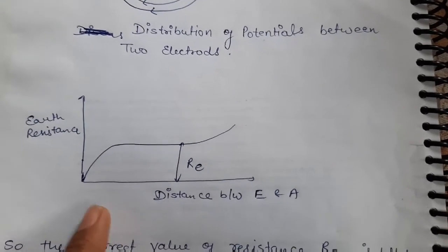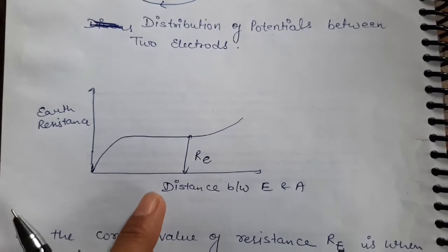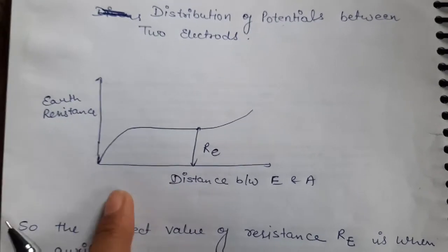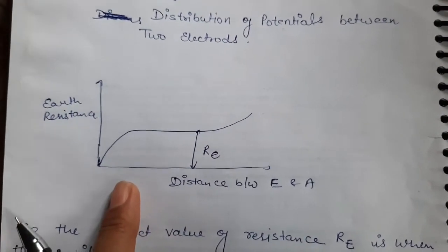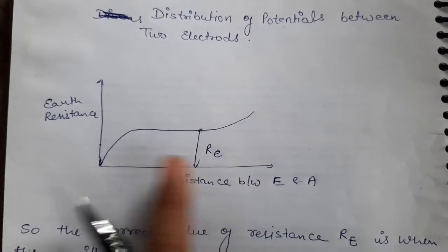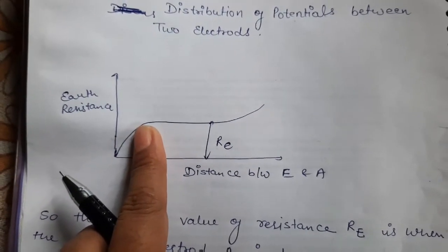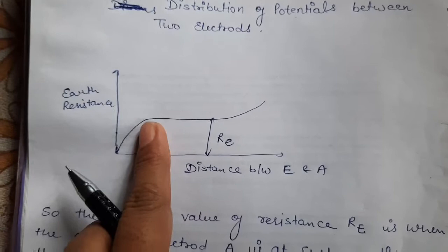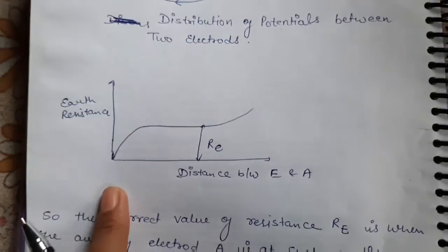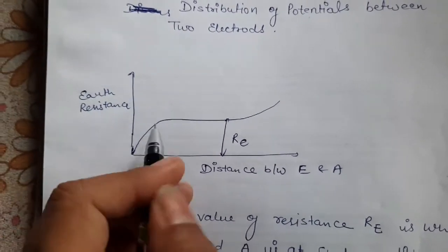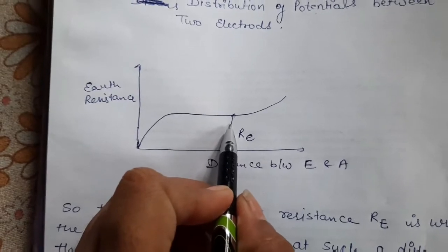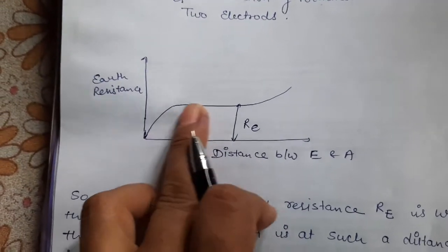This figure shows the variation of earth resistance with distance between E and A. Initially when the distance increases, earth resistance rises. In the middle part, the earth resistance is constant. Then again in this part, the earth resistance increases.